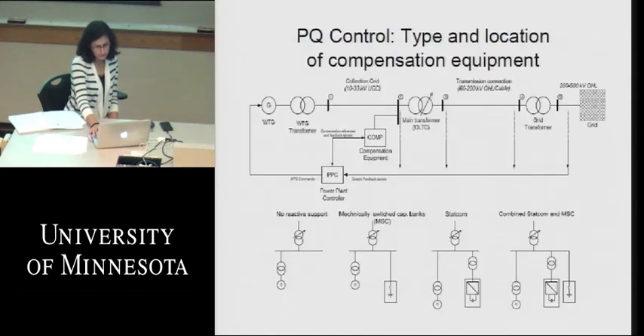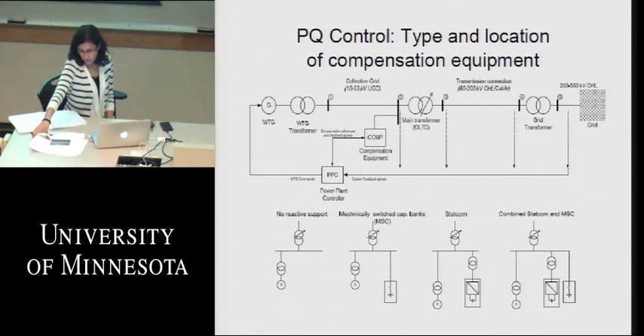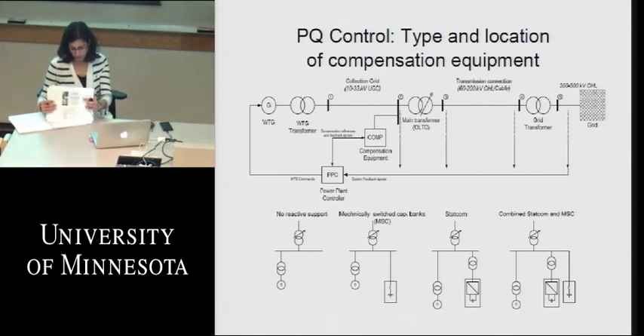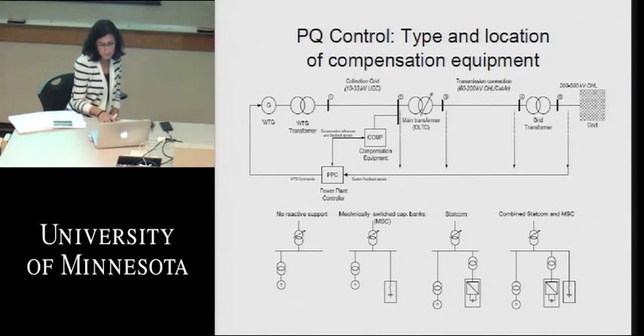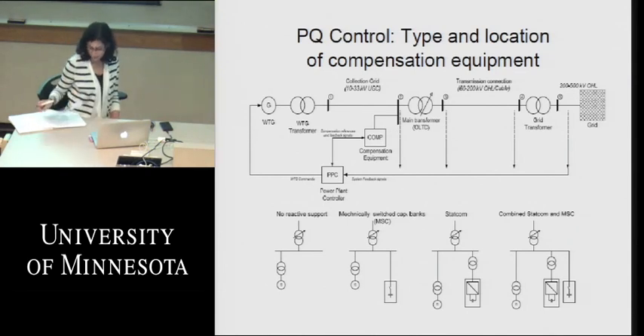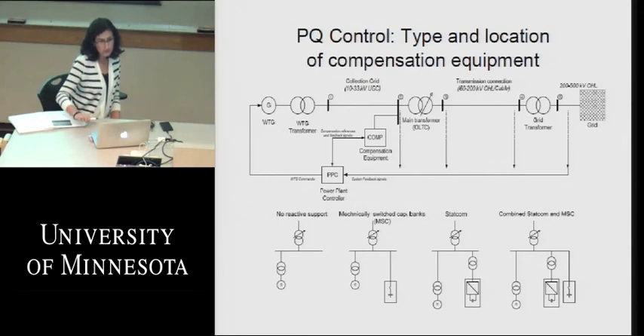And the next slide is the PQ control on the project level. I talked about it on the turbine level, but on the project level, what you'll see here is the wind turbine and then the compensation equipment and where we might put the compensation equipment. On the bottom left, it says no compensation equipment. Going to the right, we see where we can provide compensation just with switched capacitors. Next to the right, we can do the compensation with just STATCOMs. And on the far lower right, we can see a combination of STATCOMs and switched capacitors gives us the most cost-effective means for a wind power plant control solution for voltage control.